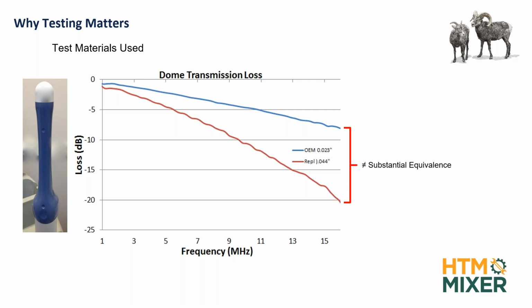We noticed that the cap's coloring looked a little suspicious to us. So we took that off and we put it in our acoustic tank, and we looked at dome transmission loss as a function of frequency. Here's the loss over here. This is how the OEM probe behaved. Here's what the material made by another company did, and that explains the lack of depth of penetration. And so that does not equal substantial equivalence. They want to see lines of identity that lay on top of each other in close proximity. When they see something like this, it's not substantial equivalence.